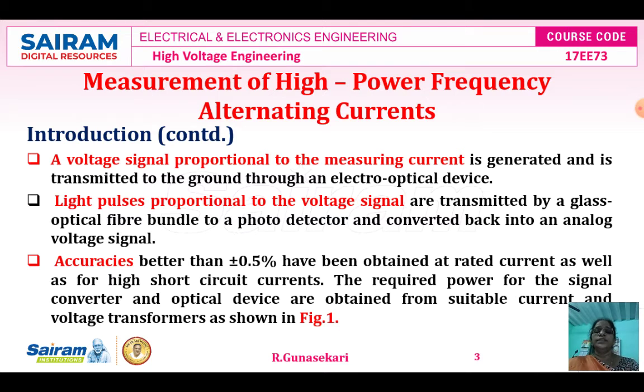A voltage signal proportional to the measuring current is generated and transmitted to the ground through an electro-optical device. Light pulses proportional to the voltage signal are transmitted by a glass optical fiber bundle to a photodetector and converted back into an analog voltage signal. Accuracy of plus or minus 0.5 percentage has been obtained at rated current as well as for high short circuit currents.